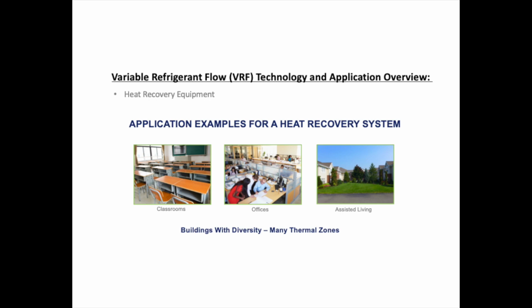its flow selector box. So where would you use heat recovery? Basically any building that has multiple zones that typically wouldn't be used or would have different load profiles. So office buildings would be a good example, assisted living, schools, universities, dormitories, mid to high-rise, multifamily. These would be good applications of using heat recovery, as you can serve all of the different spaces, but they don't all have to be either on or off at the same time, and they don't have to be in the same mode of operation at the same time, either heating or cooling. So this is what allows heat recovery systems to be very energy efficient.